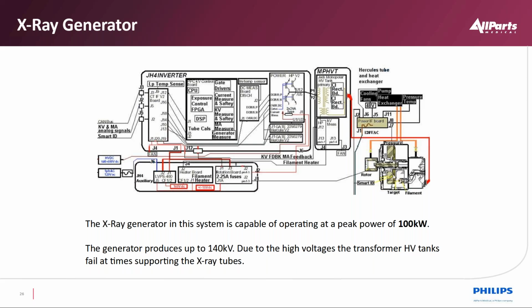So this generator is 100 kW, so we know 2 kW will become X-ray, the other 98 kW will become heat. So obviously a lot of fans in the gantry, making sure the room is environmentally good with dissipating the heat. And we have, obviously, we get high voltage arcs from the X-ray tube, but also the high voltage tanks and even the high voltage cables. So we have to be very delicate in dealing with all this material as well.